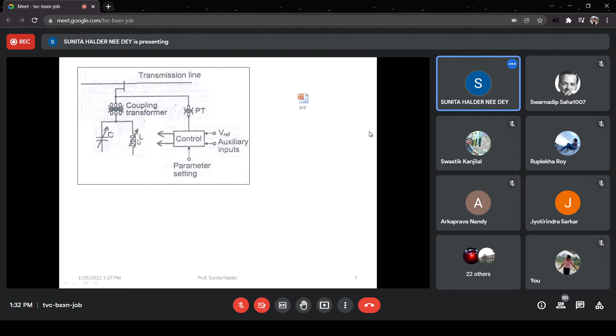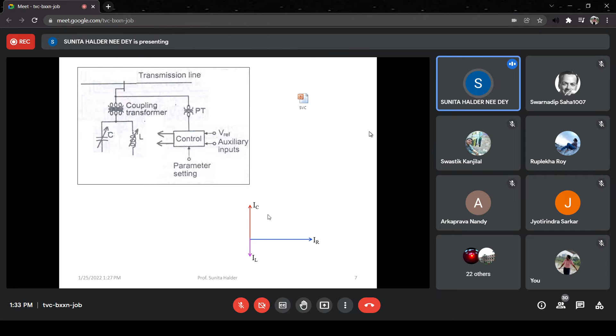Next, compensation is also required to control the power flow through a transmission line. Whatever shunt compensation I have discussed till now, say static Var compensator, the synchronous condenser, or just an ordinary inductor or capacitor in parallel, in all cases the purpose was to control the voltage, to maintain the transmission line voltage drop to a specified value. Now you see, if we want to find the expression of power flow through a transmission line, we find the expression of current, (Vs minus Vr) by jX, assuming Vr is the reference phasor, so Vs at an angle delta minus Vr by jX. We can separate it into real and imaginary parts. The total power is Vr Ir conjugate. From there, we shall get two parts.